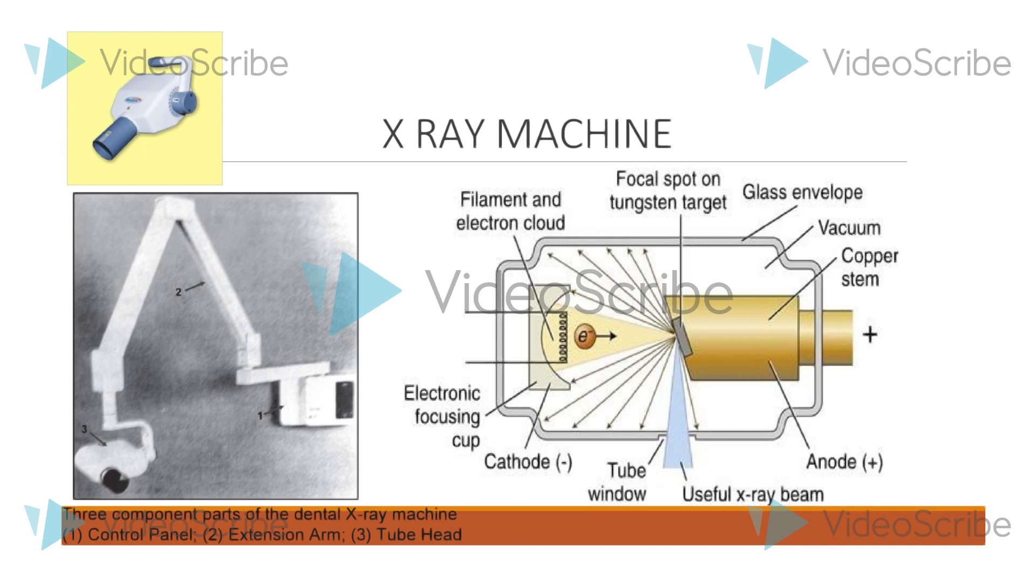Focal spot is the area on the target which the focusing cup directs the electrons and from which the X-rays are produced. Small focal spot size greater the sharpness of the image.